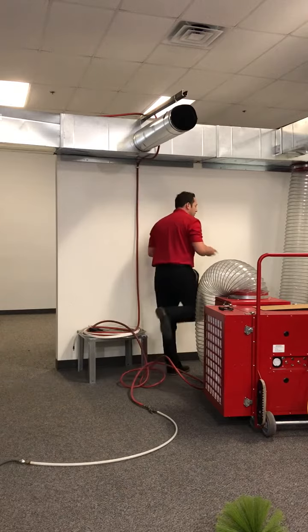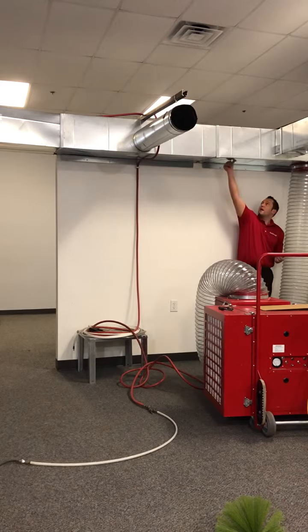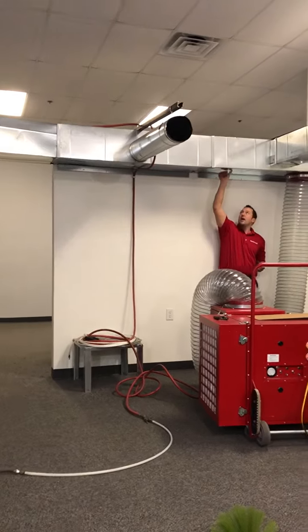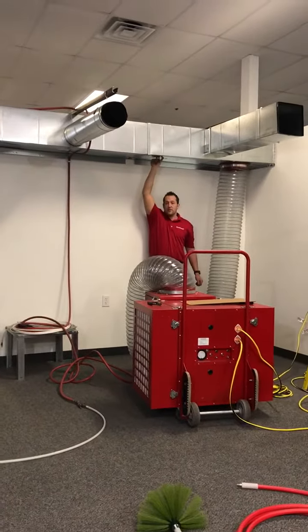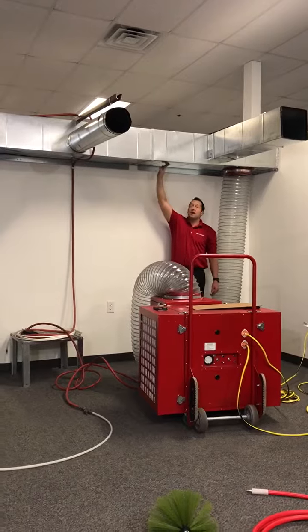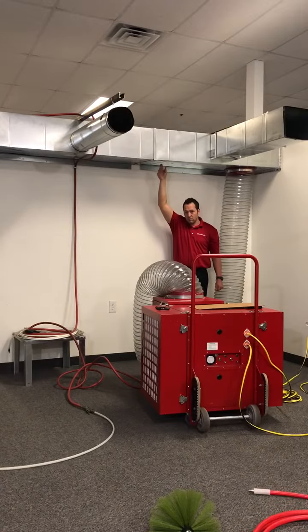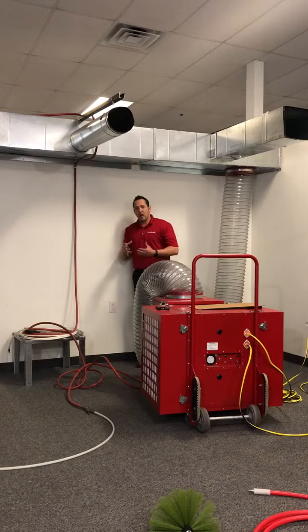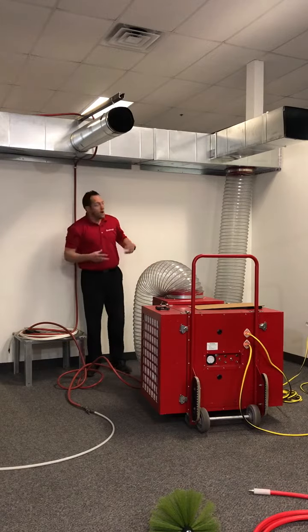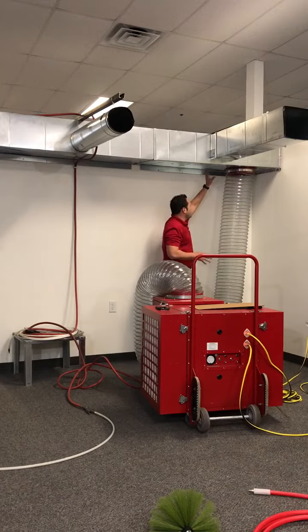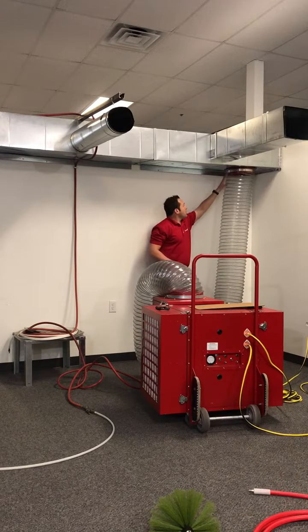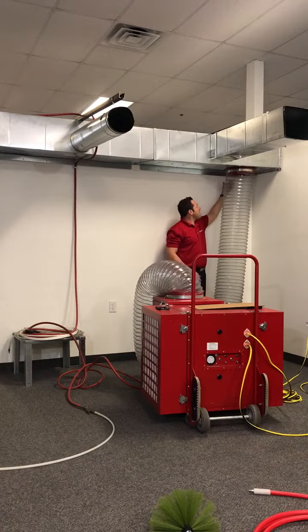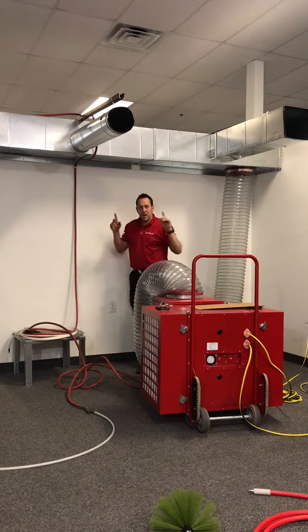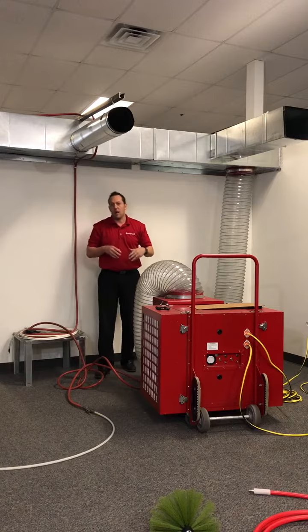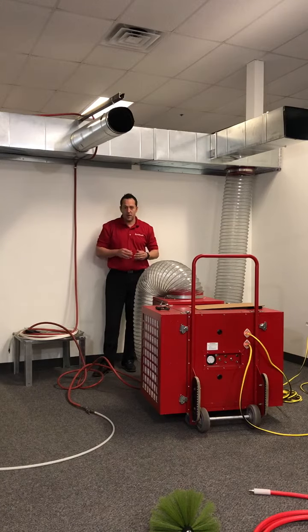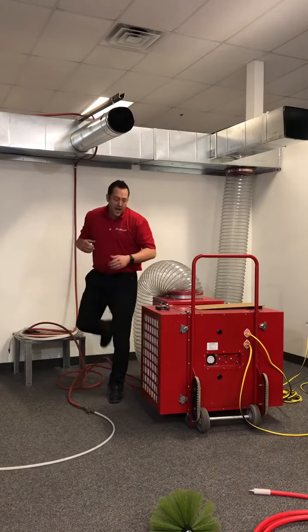Now again, in your package you may or may not have received plugs. They're 1-inch plugs to actually seal the hole that you put up. And then, depending on the state you're in, you're going to take the aluminum tape, HVAC tape, and cover the hole and seal it back up as well. So that's the actual process whenever you go through and clean the air ducts. Once you're done cleaning the system itself, you'll pull the self-tapping screws back out. Then again, you can put a 12-inch plate on top of it and seal it up with your state-required tape, depending on which one it's going to be. And then at that point, you're done.